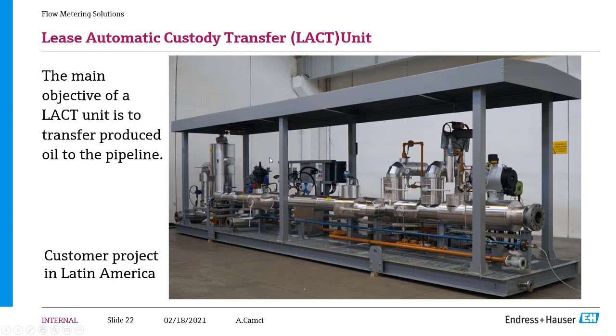This is the diverter valve. If the water cut is above a certain limit, so-called 1%, this diverter valve will quickly divert, fast-acting, the flow from the pipeline to another tank, a buffer tank. Here you see the Coriolis meter and the transmitters. At the back you don't see, but there is a small volume piston prover installed on the system together with the control valve, skid frame, drains, and canopy. This is a complete LACT unit manufactured by Endress Hauser Engineering and Production.